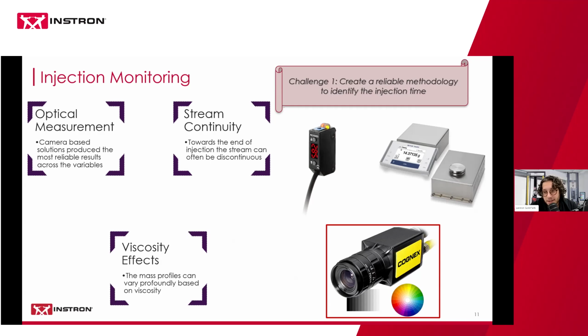So we've had the opportunity to test devices using all three methodologies, and we've found that the optical measurement using a camera is the most repeatable and robust way to measure injection time to serve the largest range of different devices. Some of the downsides of using scales, a gravimetric type of system, is you're relying on the scale data to determine the start and end of injection, especially if you're dealing with high viscosity fluids where there is a slow rise to a plateau in the scale reading. It can be difficult to decide what is the end of the injection. There's no clear point in the data.